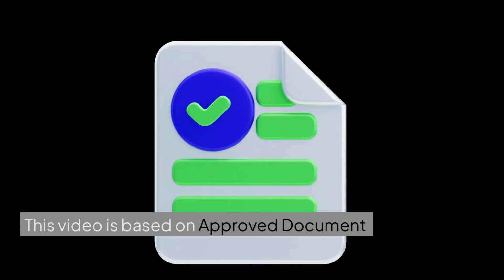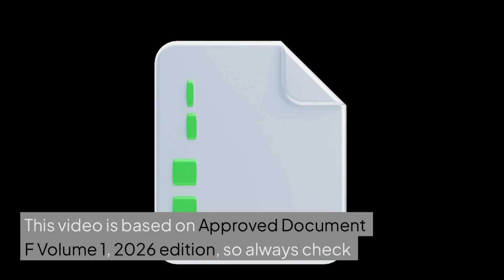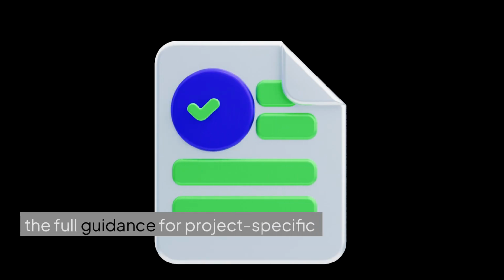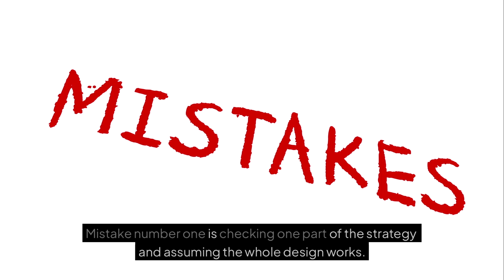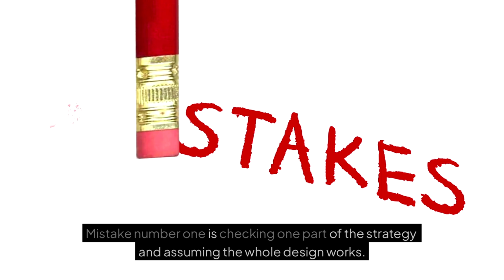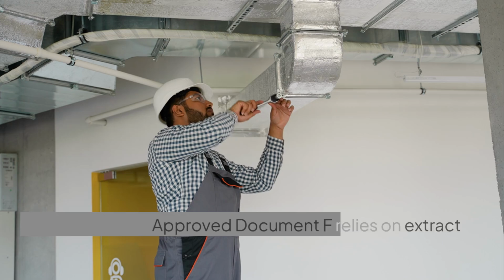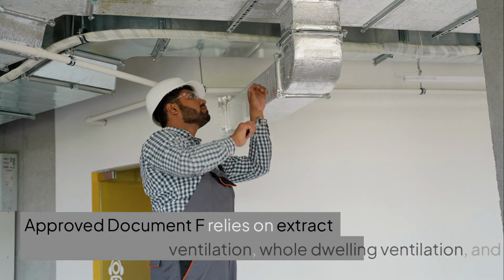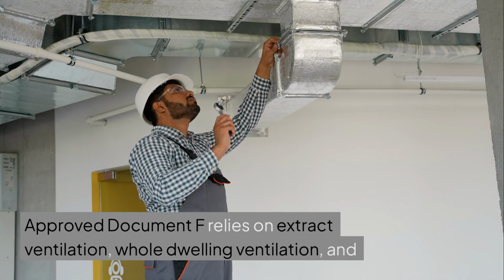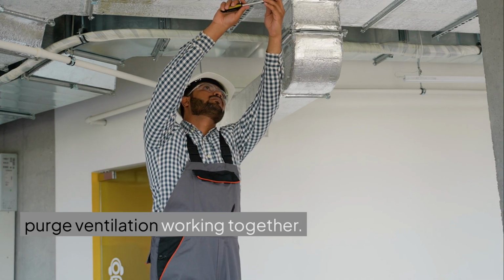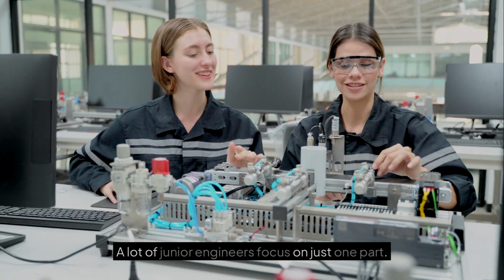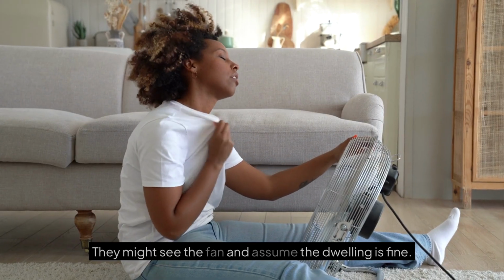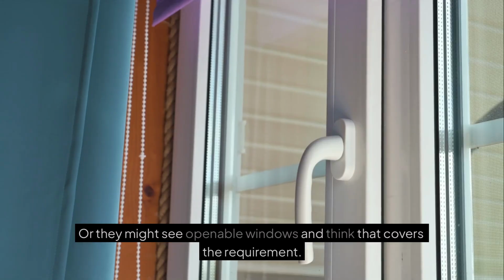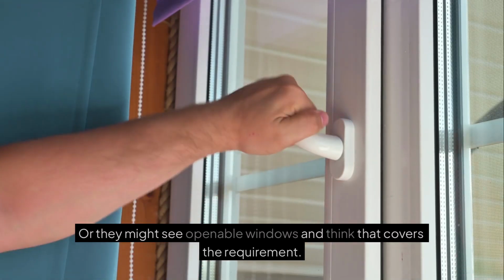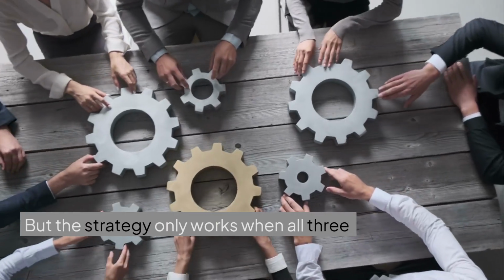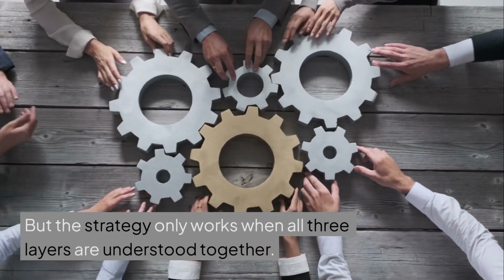This video is based on Approved Document F Volume 1, 2026 edition, so always check the full guidance for project-specific compliance. Mistake number 1 is checking one part of the strategy and assuming the whole design works. Approved Document F relies on extract ventilation, whole dwelling ventilation, and purge ventilation working together. A lot of junior engineers focus on just one part. They might see the fan and assume the dwelling is fine. Or they might see openable windows and think that covers the requirement. But the strategy only works when all three layers are understood together.